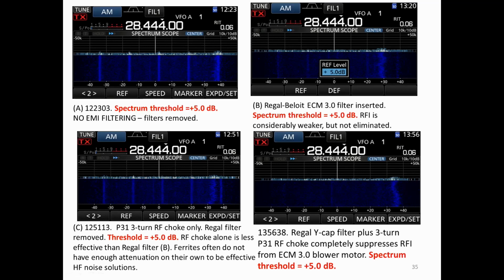Here I actually took the capacitor filter, the common mode filter, out, and I put the RF choke in only. If you compare C with A, you'll see that the ferrite choke filter alone reduced the RFI considerably, but again, not completely. But interestingly, if you use both together, it pretty much completely suppressed the RFI from the ECM3 blower motor. And that's the arrangement I have now. I have a 3-turn type 31 ferrite RF choke, followed by this Regal YCAP filter. And I have a very nice RFI-free system.